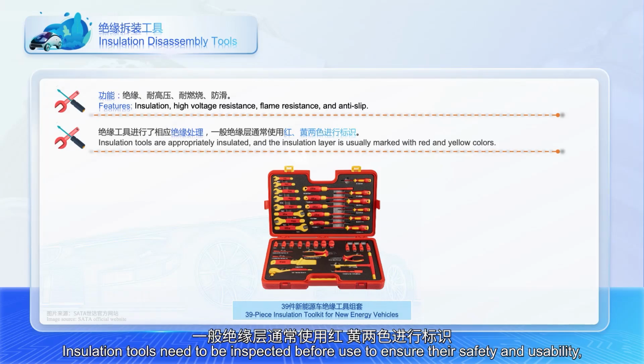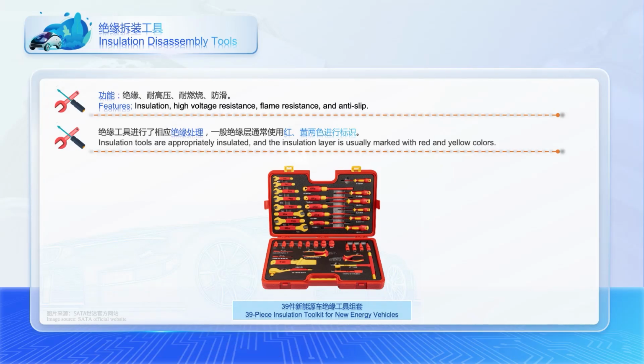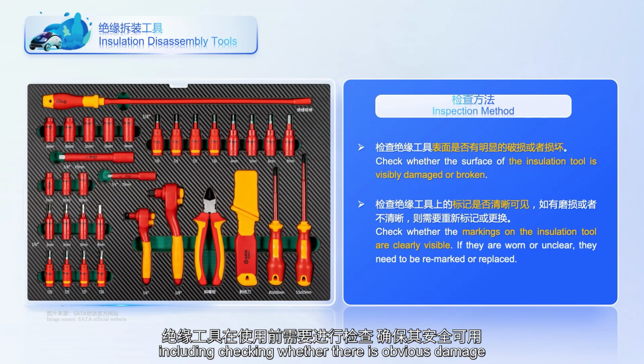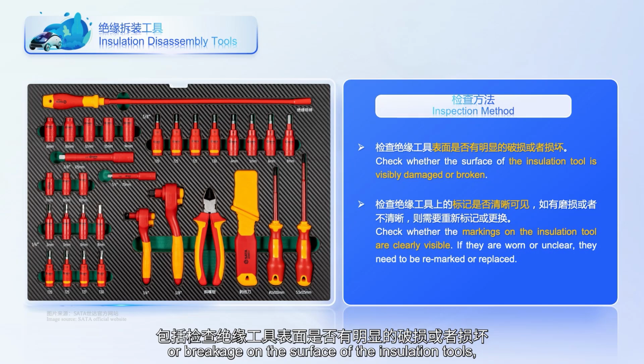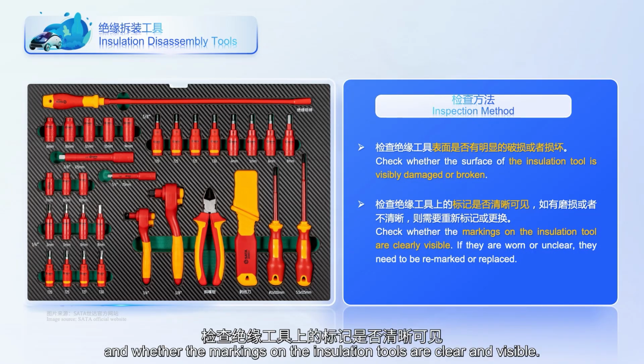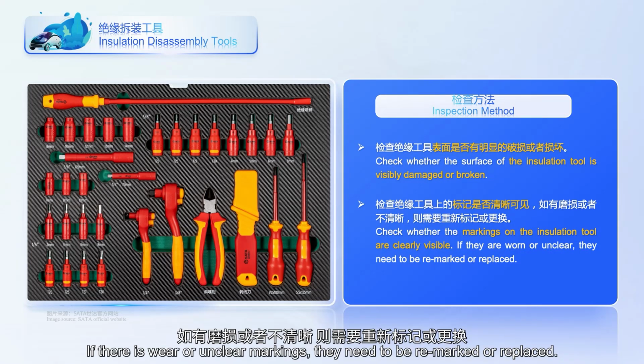Insulation tools need to be inspected before use to ensure their safety and usability, including checking whether there is obvious damage or breakage on the surface of the insulation tools, and whether the markings on the insulation tools are clear and visible. If there is wear or unclear markings, they need to be remarked or replaced.